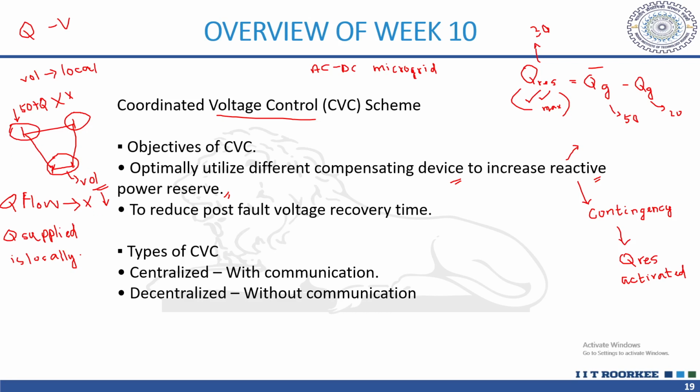So what is recommended is that we maintain the Q reserve in this area so that whenever required, this Q can be supplied locally in these sub areas. This is also in different standards in India. It is mandated that you never transfer Q between areas over long distances.